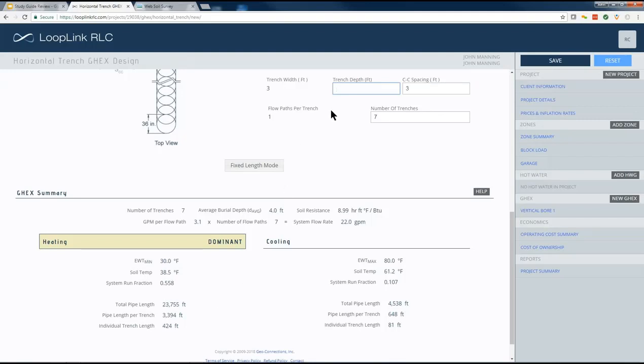So let's see what happens if we go from a 4-foot depth to an 8-foot depth, just to show you the impact there. Now look what happens to our predicted soil temp. It's 47 degrees instead of 38. So we basically doubled the amount of delta T that we allow between our loop and the soil. And you can see what happened to the total pipe length: 13,500 feet, down from the 25,000. Same thing for the pipe length per trench and individual trench length here. Had a huge impact.